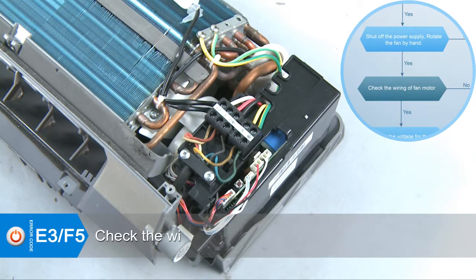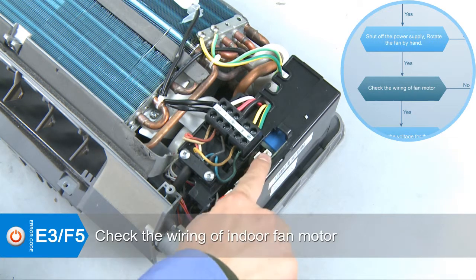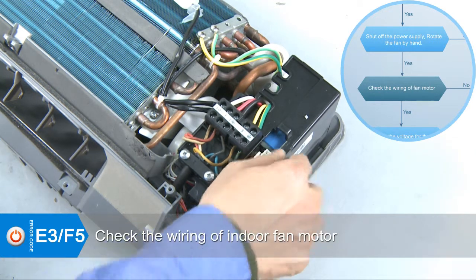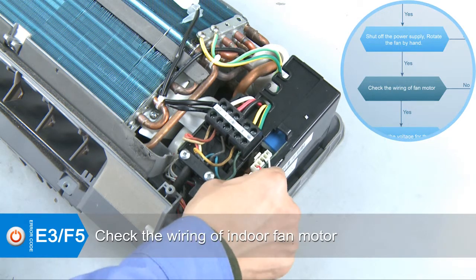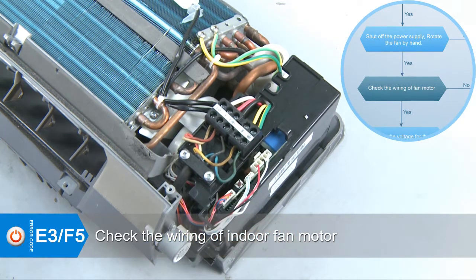Examination for the indoor fan motor. Taking AC motor with feedback as an example, it has 2 pins. Separately, the 3 cores pin connects to the power supply and the 5 cores pin is used for signal transmission. If the connection is correct, check the fan motor.